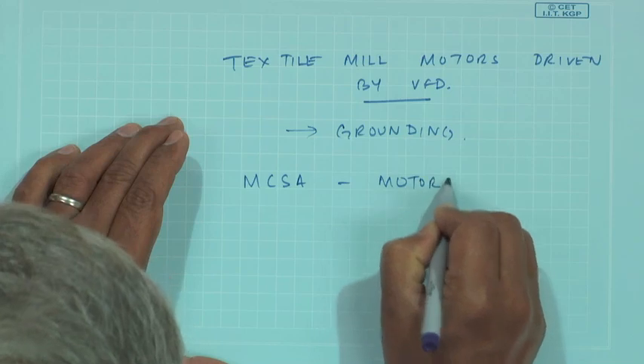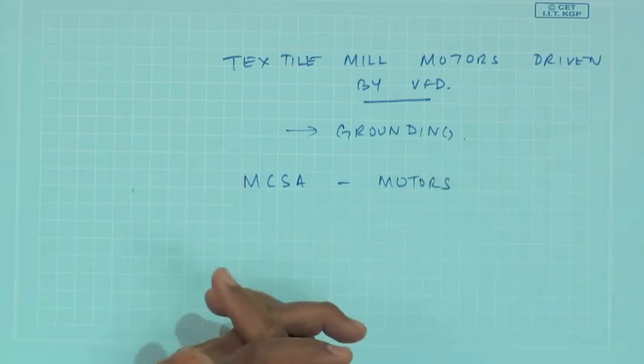To summarize fault detection techniques using MCSA for motors: we can find faults due to broken rotor bars, stator eccentricity, bearing faults, and bearing seat damage caused by high-frequency sparking from transients produced by VFD drives in electrical motors.